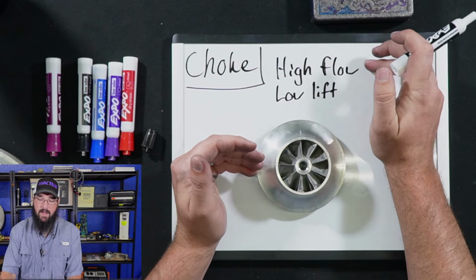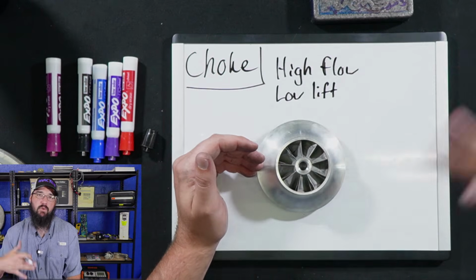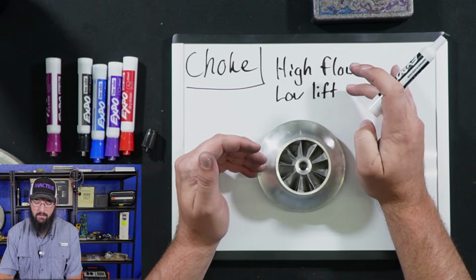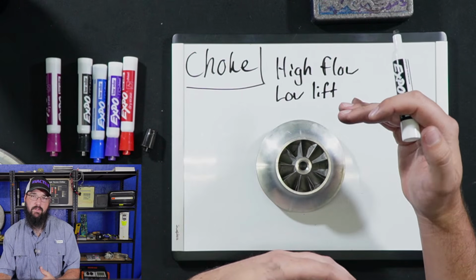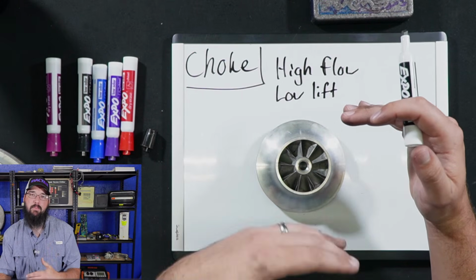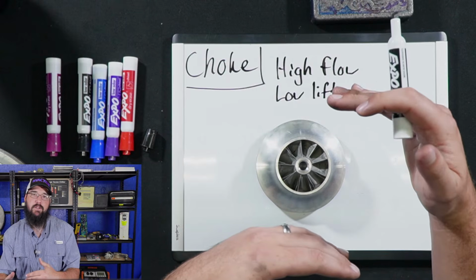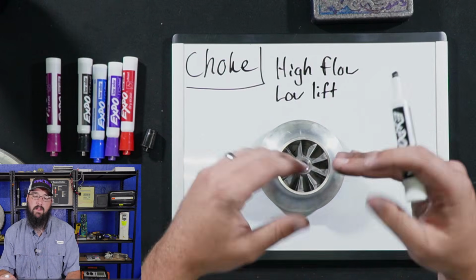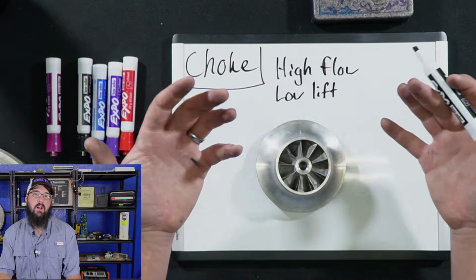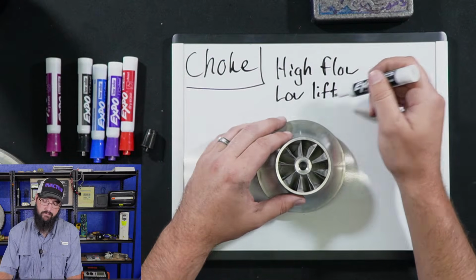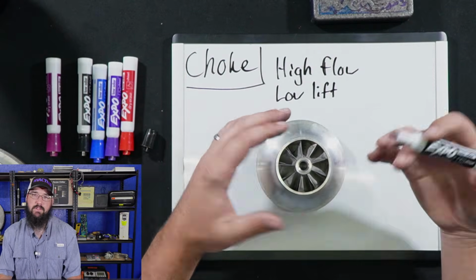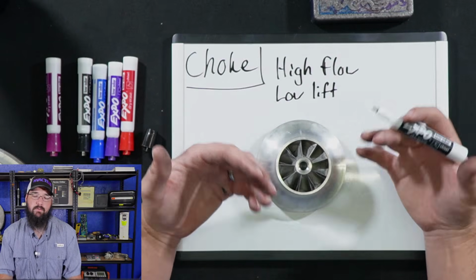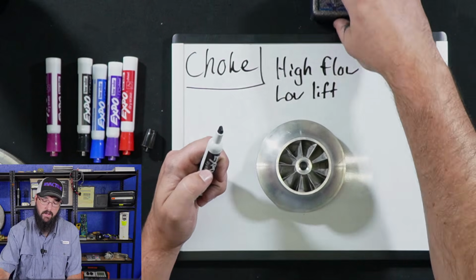We have really high flow through the impeller, meaning we're moving lots of refrigerant, but we don't have a whole lot of lift. So our evaporator pressure to discharge pressure is really low. You get just the right combination of that, and we will put the impeller in a choke position, which is not good for it. We do not want to do that.